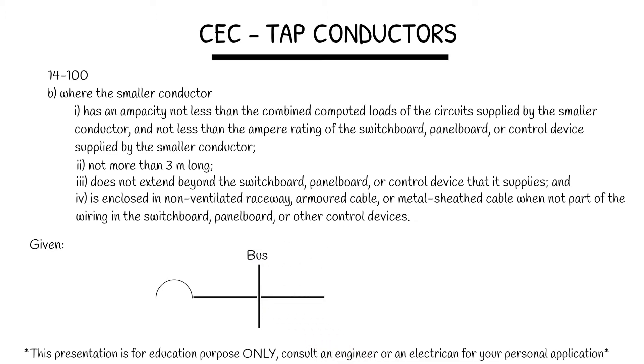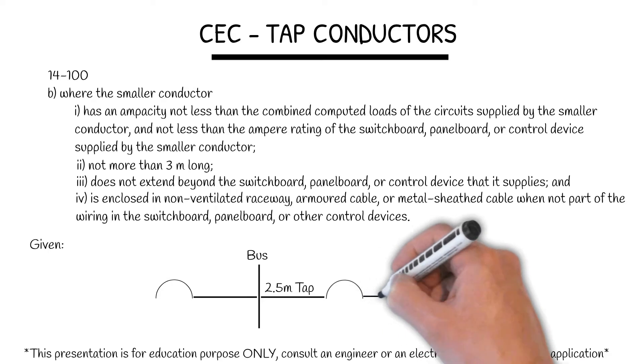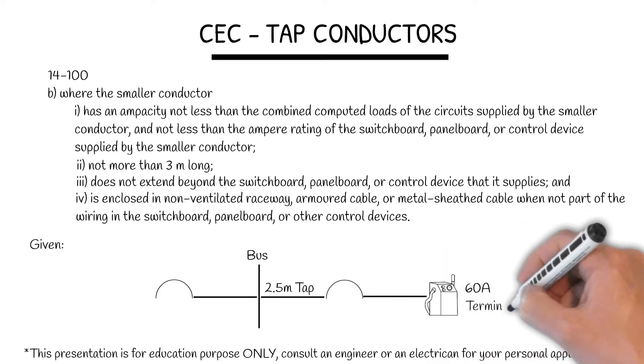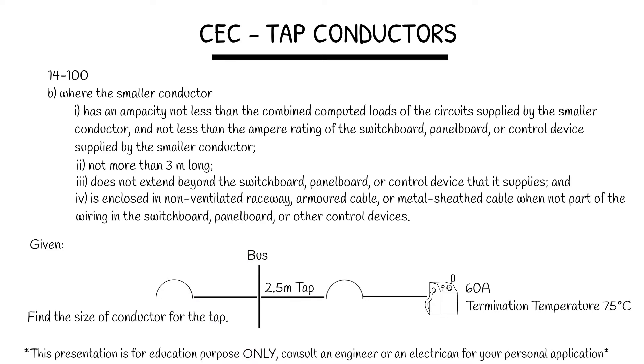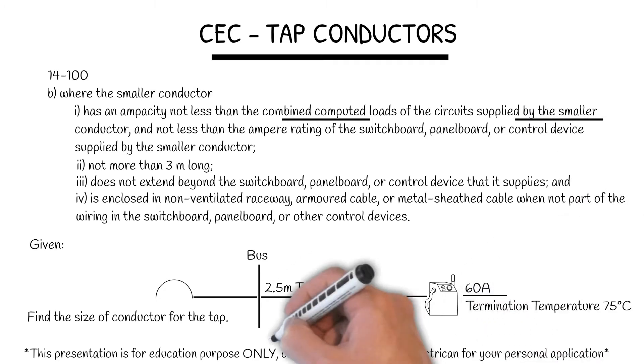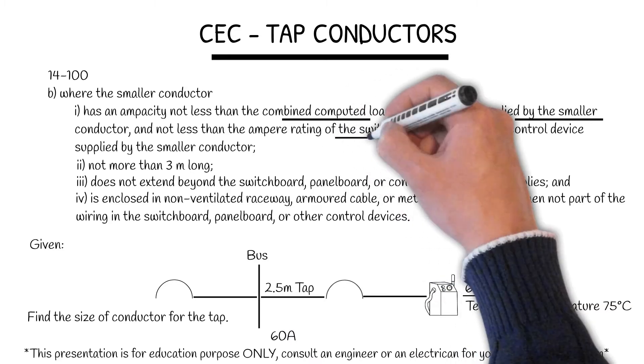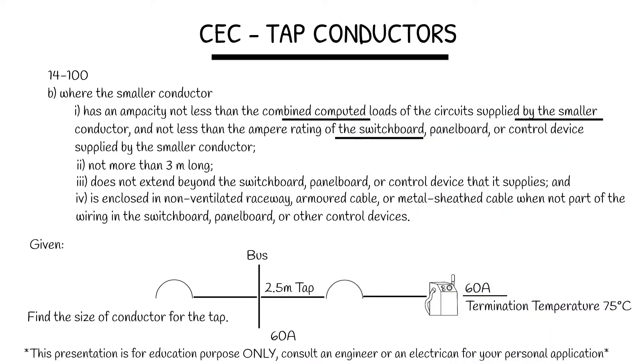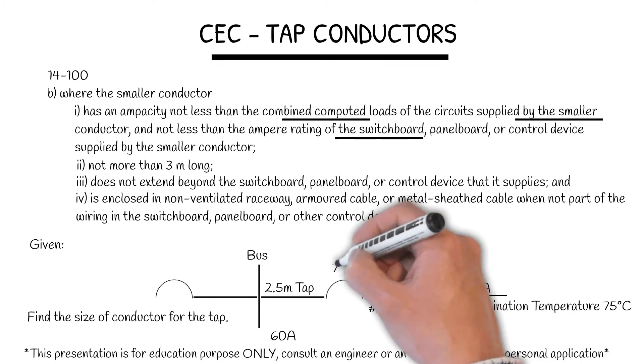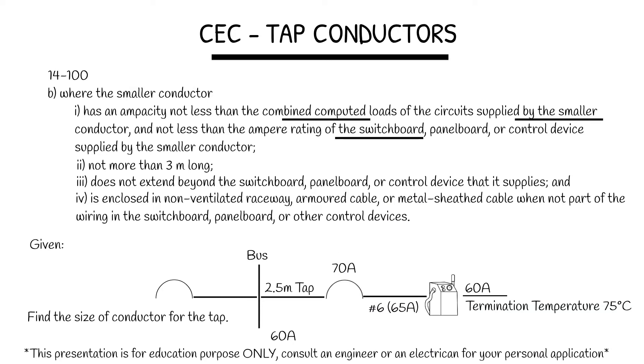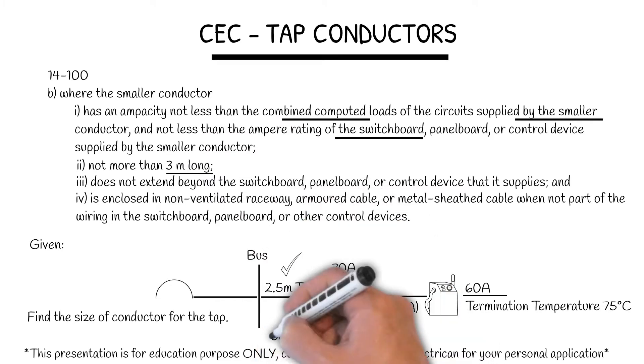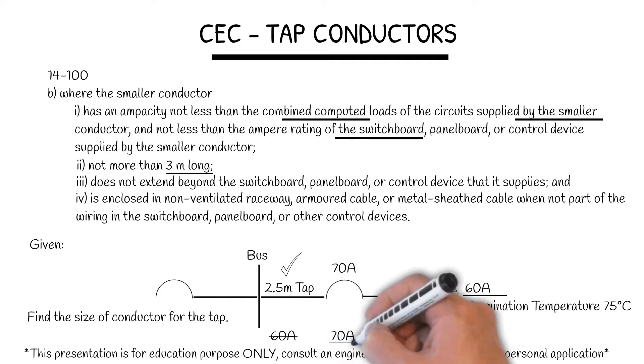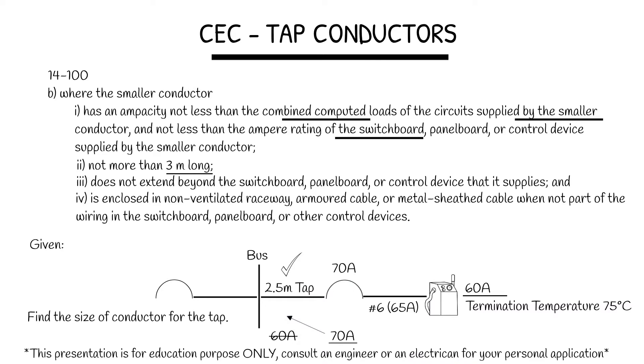This is our bus. We have a 2.5 meter tap. This is our load. We draw 60 amps with a termination temperature of 75 degrees Celsius. Find the size of conductor for the tap. Not less than the combined computed loads supplied by the smaller conductor — that's 60 amps. It has the ampere rating of the switchboard. To find that, we must size the wire first, which is number 6 for 65 amps, and size the overcurrent device at 70 amps. Therefore the switchboard is 70 amps. It's not more than 3 meters long, which we are okay. Therefore the larger of the two values is 70 amps, so our wire size for the tap would be number 4, good for 85 amps.